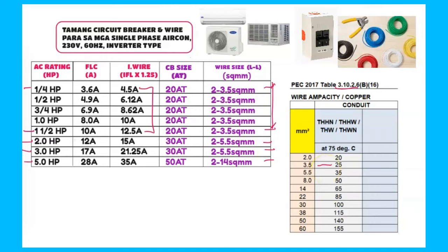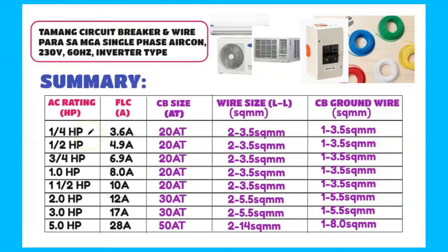12.5. And then, yung 5.5, ang kaya niyang capacity is hanggang 35 amperes. So, ang 8.0, kaya niya hanggang 50 amperes. So, itong 14 square mm, ang kaya niya is until 65. Itong 22 square mm, ang kaya niya is until 85. And then, meron pa itong sunod. At 60 square mm, ang kaya niya is until 155 amperes. Okay? We're almost done with our computations.